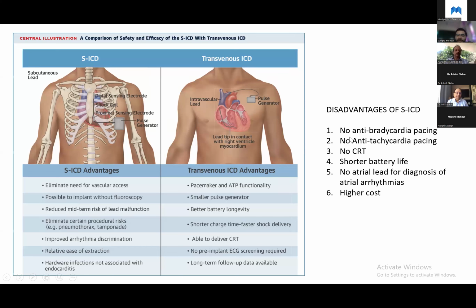At most, after the shock is delivered, it can pace transcutaneously for up to 30 seconds. Beyond that, subcutaneous ICD cannot pace. So that means any requirement for pacing, bradypacing, for a patient is an absolute contraindication for subcutaneous ICD.